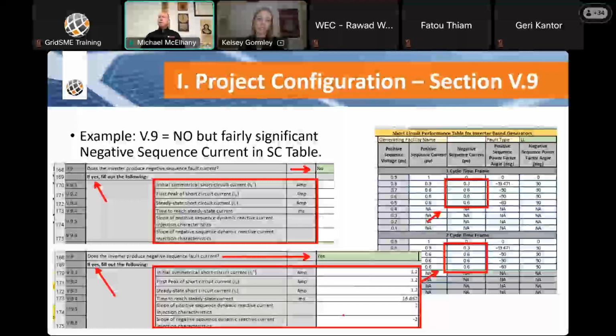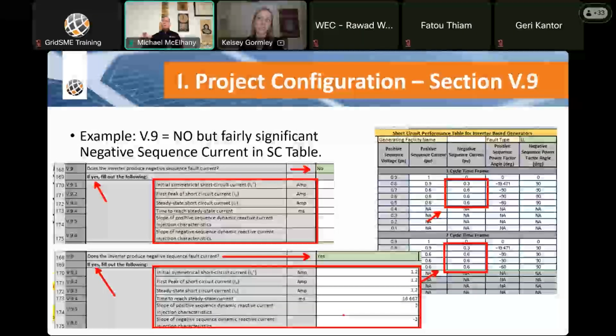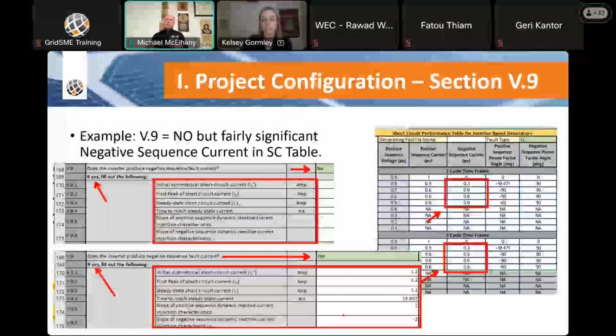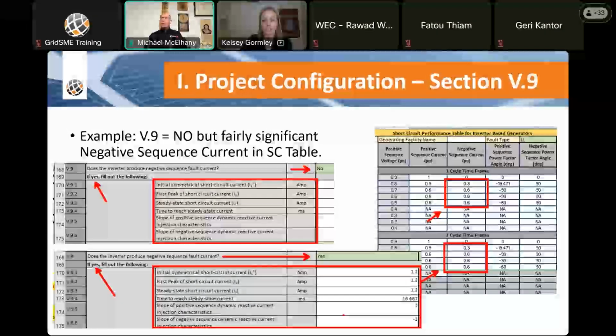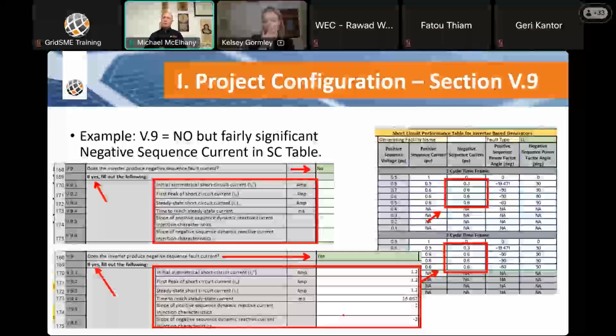And that's how we found this Tesla one. So we said no, and CAISO questioned it. We went back to Tesla and they said, well, yes, it does. And they provided the V.9.1 through V.9.6 answers that are required if you do say yes. So every time we see a no with significant or semi-significant negative sequence fault current for line-to-line or single line-to-ground faults, we have the conversation. If it's the same model we've already answered, we just get a confirmation. If it's a model that we haven't gotten the confirmation on, we confirm with the inverter manufacturer.